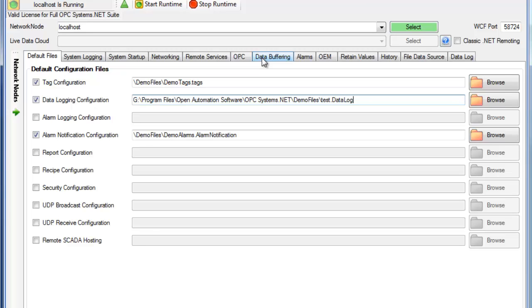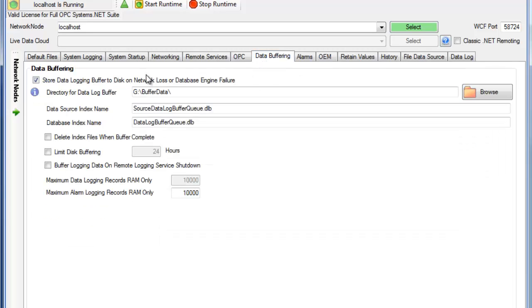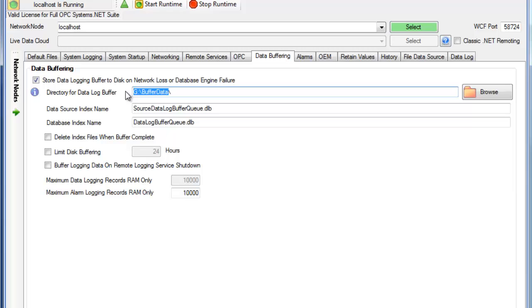Under the Data Buffering tab, there's one more key thing here. We want to enable this feature to set up a directory to buffer data to if there's a database engine problem or a network failure. We'll buffer all of those files into that directory so that you can basically have a database failure for, say, months, but all of the data will be retained and you won't lose any data in that service.